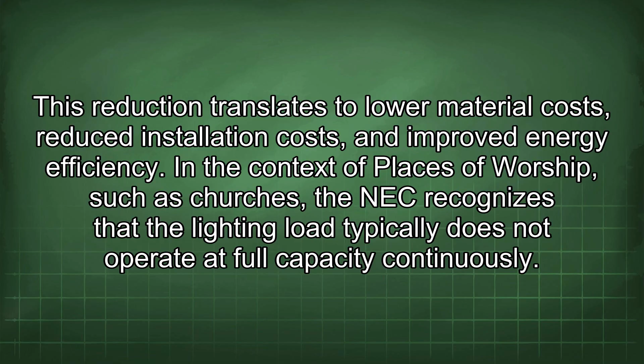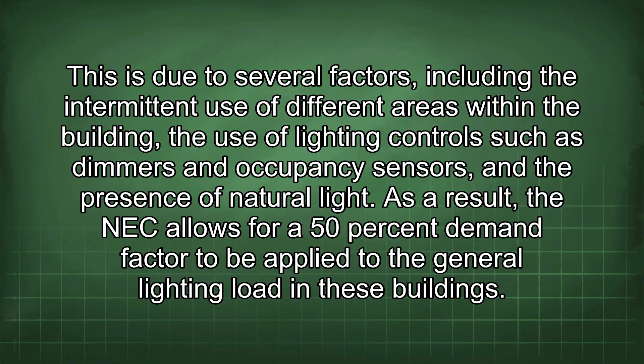In the context of places of worship, such as churches, the NEC recognizes that the lighting load typically does not operate at full capacity continuously. This is due to several factors, including the intermittent use of different areas within the building, the use of lighting controls such as dimmers and occupancy sensors, and the presence of natural light. As a result, the NEC allows for a 50% demand factor to be applied to the general lighting load in these buildings. This means that only half of the total connected lighting load needs to be considered when calculating the electrical service size. Applying the demand factor involves several steps.